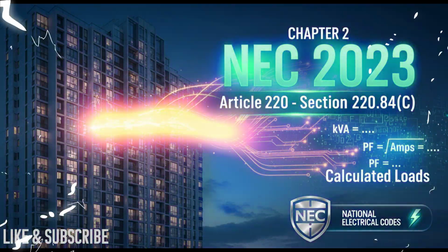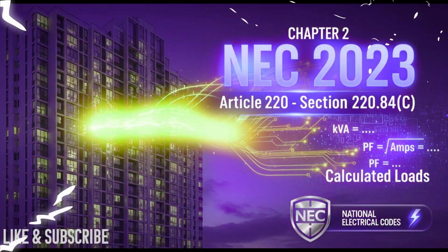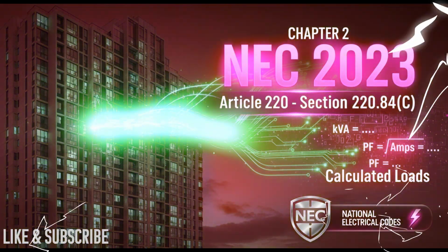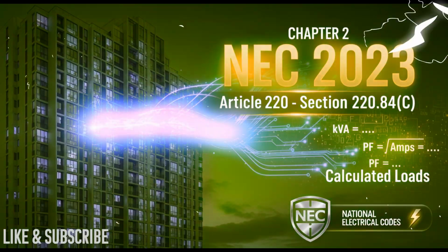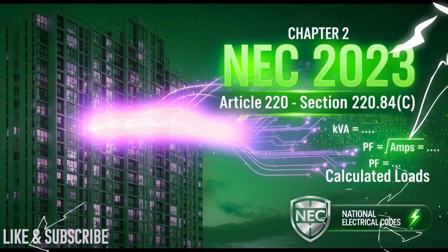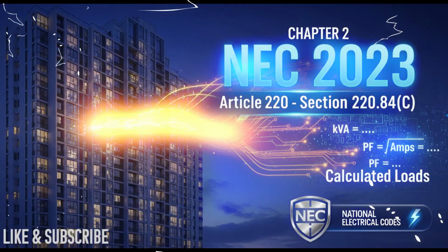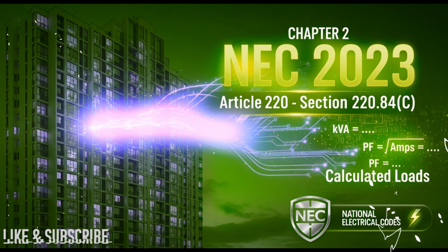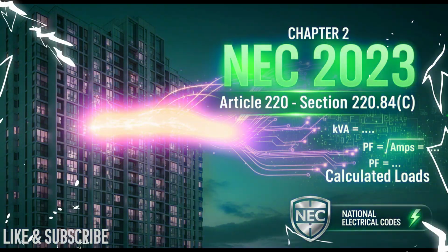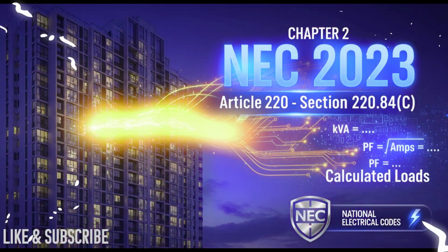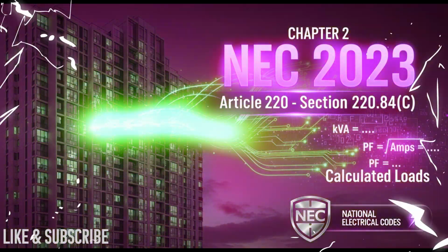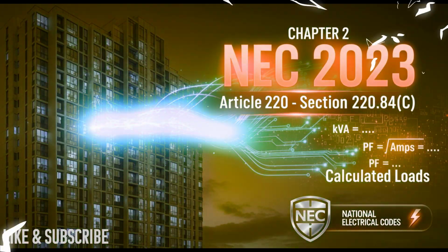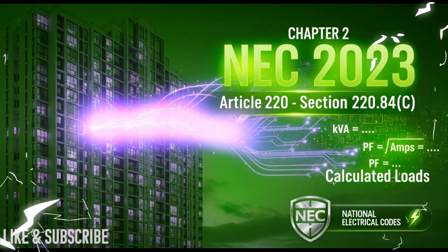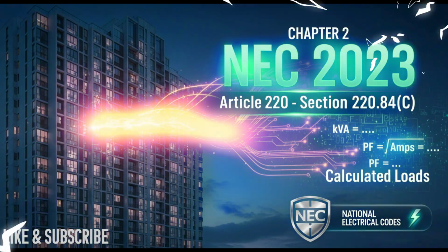Okay. So before we get into the nitty-gritty of the calculation, let's get our bearings. Where does this wiring and protection chapter fit in the whole NEC structure? Our sources lay it out. Yeah, the NEC is pretty logically put together. It kicks off with Chapter 1, General. That's mostly admin rules, definitions, stuff like that. Right. But right after that, Chapter 2, Wiring and Protection. That's our focus. And it's foundational because it sets the basic rules for things like overcurrent protection, your breaker sizes, and conductor size, your wire sizes. And those two things, breaker size and wire gauge, are kind of useless unless you know how much power you're actually dealing with. Exactly. Chapter 2 is the prerequisite before you even think about physical installation. It sets the protection rules and tells you how to figure out the load that protection needs to handle. So it's like the gatekeeper. Determines the required capacity before you specify a single wire. Perfect way to put it.